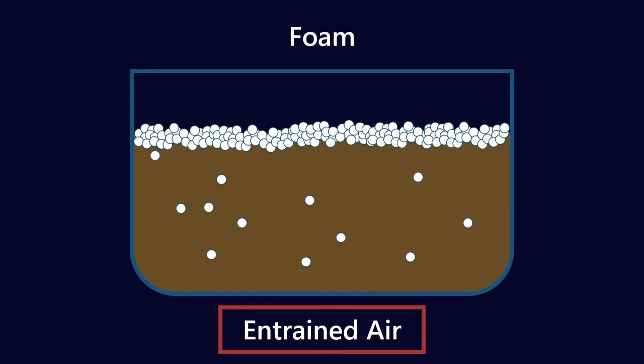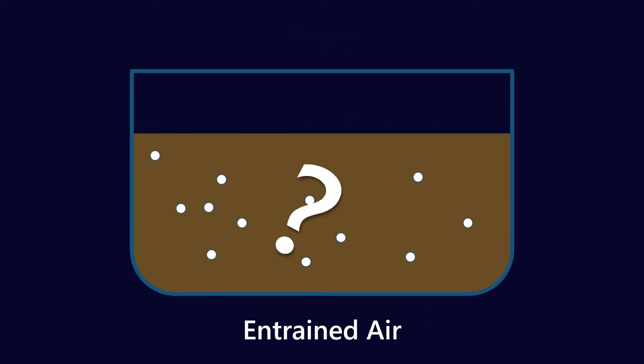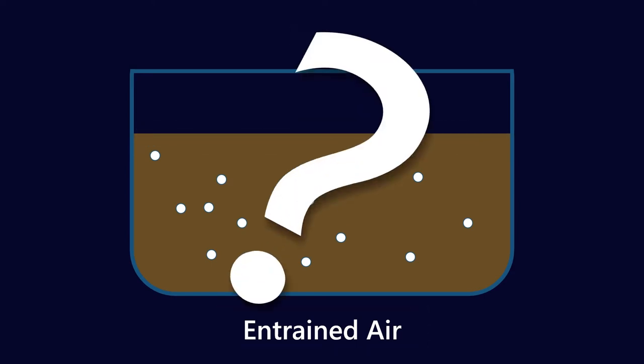Let's talk about entrained air because entrained air or significant amounts of entrained air can cause all kinds of problems. You can have cavitation, vibrations, oxidation, microdieseling, loss of pressure. All kinds of problems can result from a significant amount of entrained air. So let's talk about where entrained air comes from.